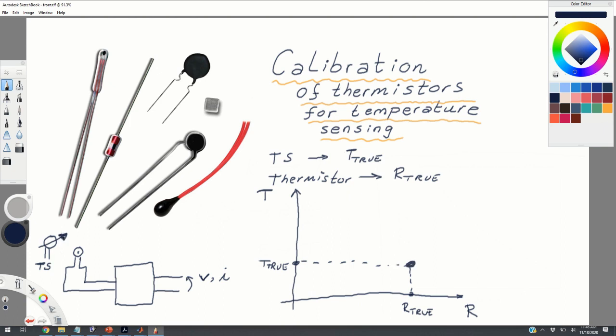What you can do next is change the temperature of the environment. For example, you can place the temperature sensor and thermistor on a hot plate and increase the temperature. Or you can place both sensors into a cup of water and start to heat it up. Using the same procedure, you can obtain a number of points for different values of temperature. In this way, you can obtain a set of calibration points by yourself. Even if you have data provided by the manufacturer, it's always good to independently obtain calibration points to test your thermistor and verify it provides reasonable readings.